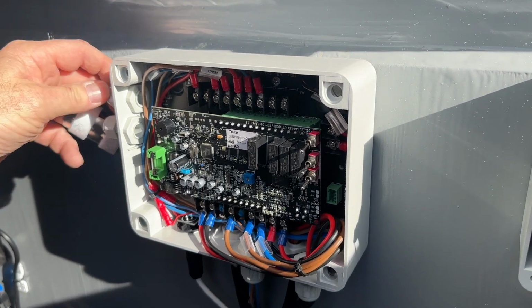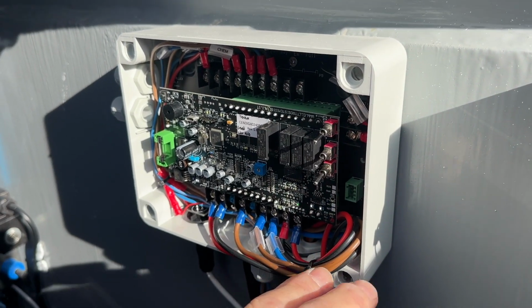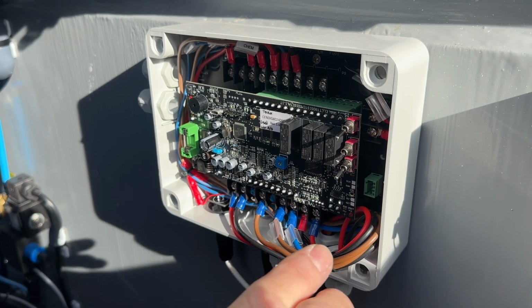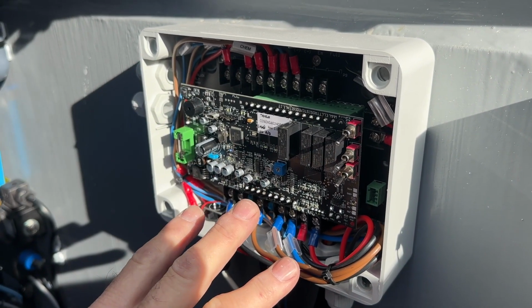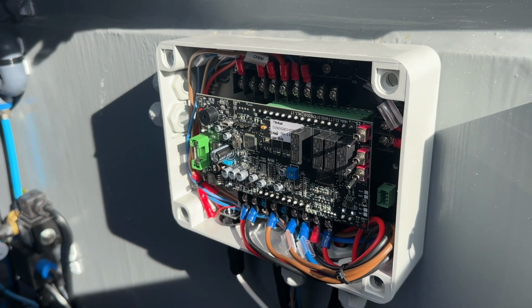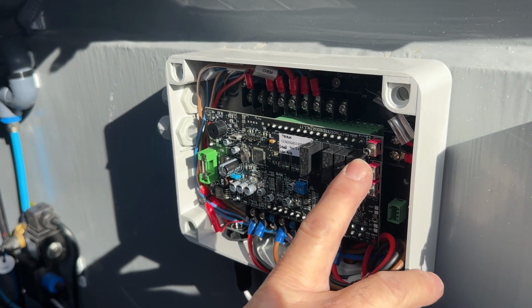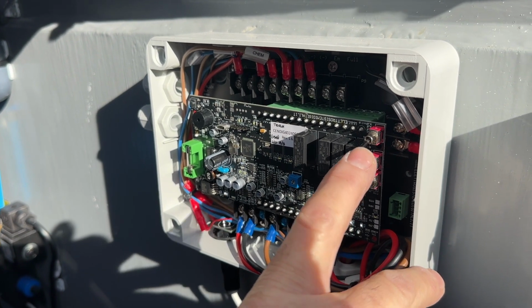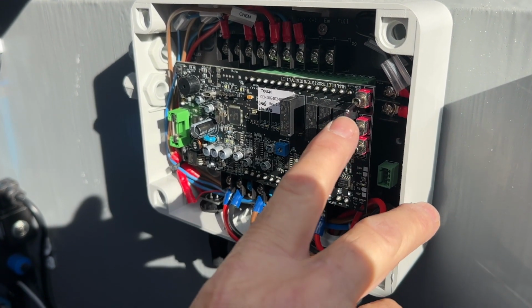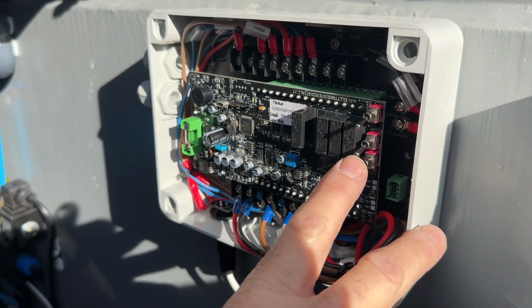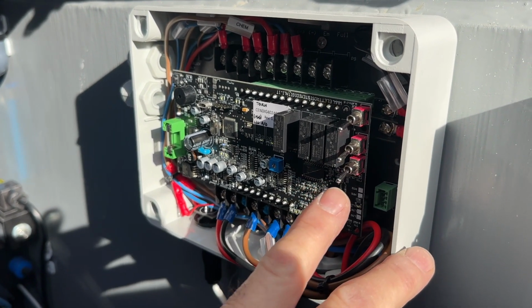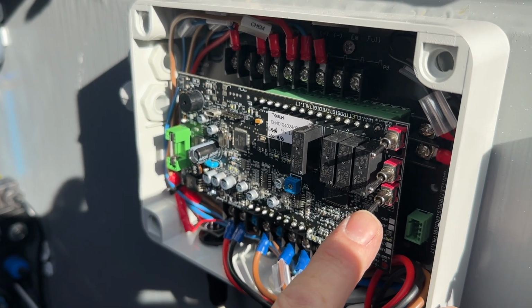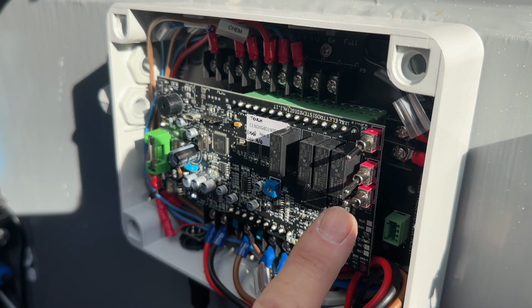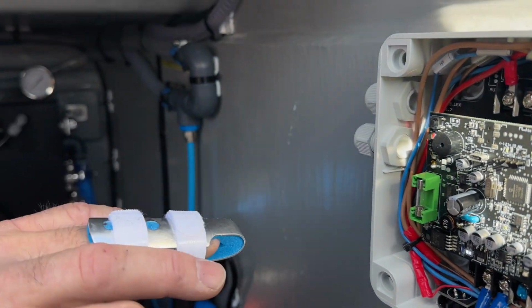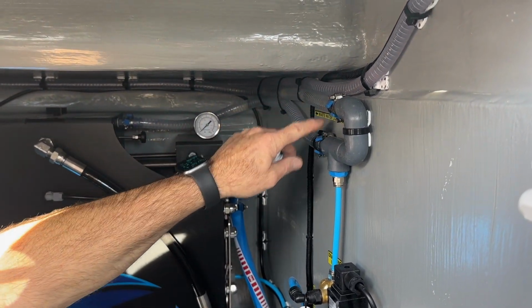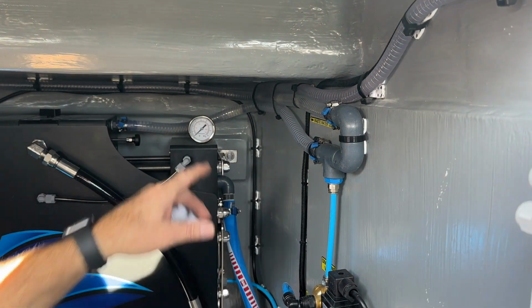Okay. So these micro switches perform the functions of the Watermaker and can be used in the event that the communication between the computer board and the panel is lost. The top micro switch activates the pump, so pushing it down, default is down, is off. By pushing it up, we'll be able to start the pump. The middle one activates the bypass function when it's up, and the bottom one activates the solenoid valve for your freshwater flushing. So when it's up, you'll see that this line's filling up with fresh water now. And that's the brine discharge line.